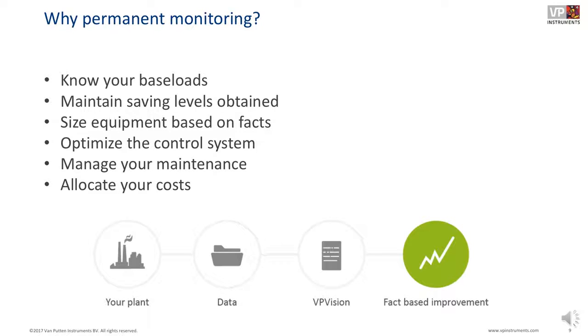Then you can start allocating your costs with monitoring. We've seen a lot of cases where companies just have an equal share being paid by their departments. Well, some departments use more air than the others. So if you want to have a fair share amount on that energy bill, put a meter in and actually measure how much air is going into which areas of the plant. And if you know what your SCFM costs or your cubic meter per hour or per minute costs, then you can start cost allocating over a period of a month or weeks or other periods that you find necessary to see how much they are using.